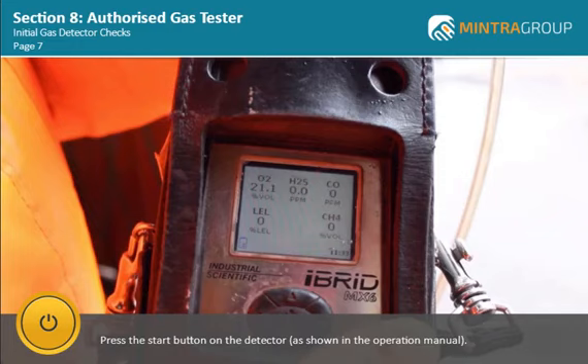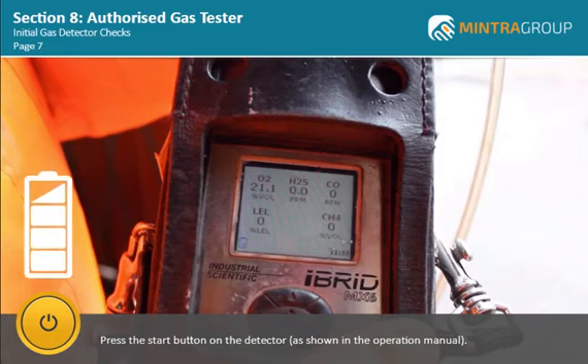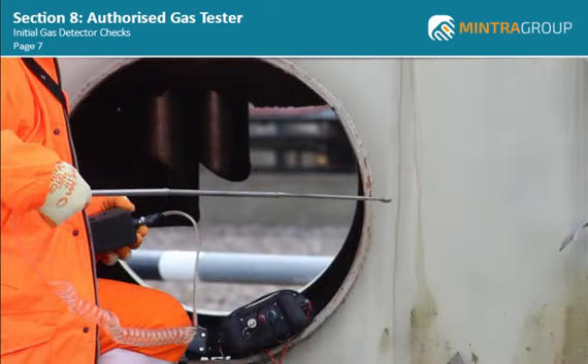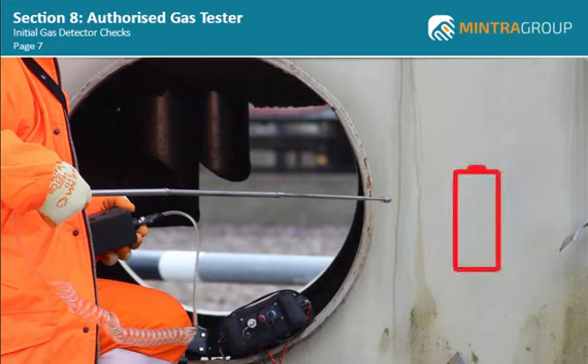Next, press the Start button on the detector as shown in the operation manual. One of the first things you will see is the amount of charge left in the battery. Always ensure that the gas detector is fully charged. This is important if you're carrying out testing of a confined space where you may have to enter a complex configuration using breathing apparatus. The last thing you need is for the gas detector to run low on battery life, and you have to exit the confined space to recharge the battery.